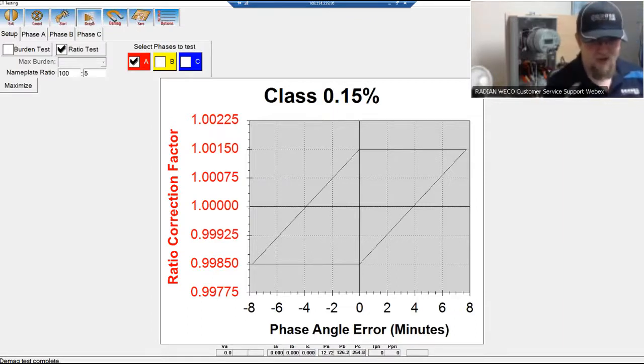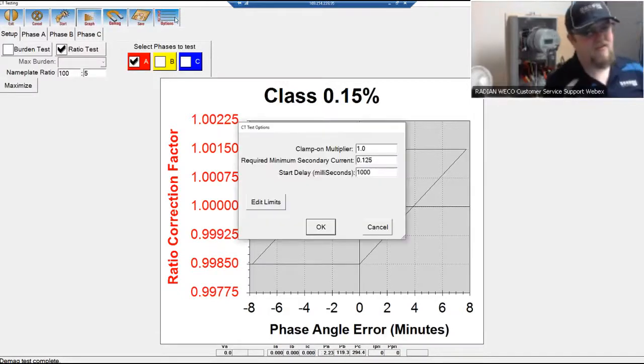Saves the results that you've run on the RW for viewing later. And then options gives you a couple different options for CT tests. If I click into options, you get three options. One is a clamp-on multiplier. So if your clamp or rope probe, sensor link probe, whatever you're using to get primary data, has some form of multiplier to it, in terms of millivolts per amp, you can put in that clamp-on multiplier here.